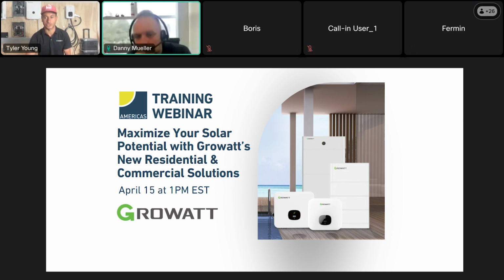Sure. The SPH 10,000 will not be Canadian service entrance rated. That's just based on the design of the unit and the input section. So you would need to use it as a connection to the electrical panel of the customer, or use a small backup panel or critical loads panel as the backup system. Yeah, it's probably not a product that you'd use in a typical residential application for full home backup, as it is only a 60 amp transfer switch in there, not a 200 amp. That's what the 200 would be better for still. Exactly. So it's more of an off-grid product, or maybe some low cost or competitively priced battery backup for just some things, but not full home backup.